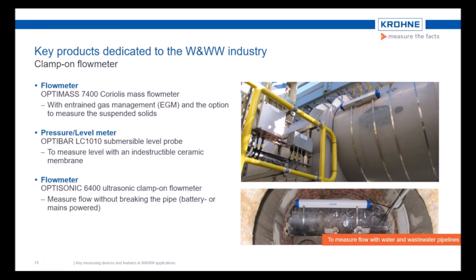Those clamp-on devices are made for permanent use, but mostly used as a control measurement to check certain processes and flow rates or consumptions. The device can be used in three different size versions, which cover small diameters such as diameter 15, half an inch, up to big diameters up to diameter 4000, which is 160 inch.